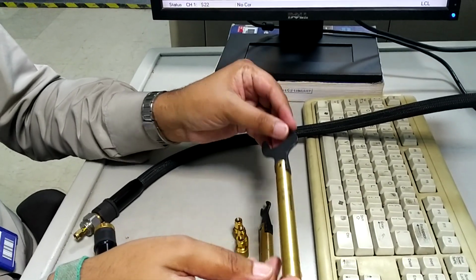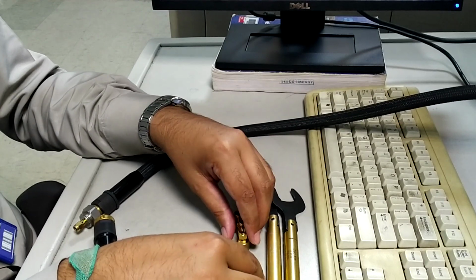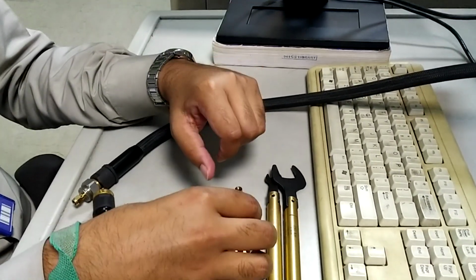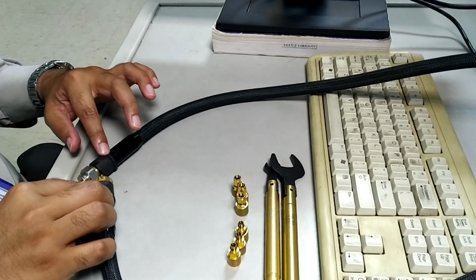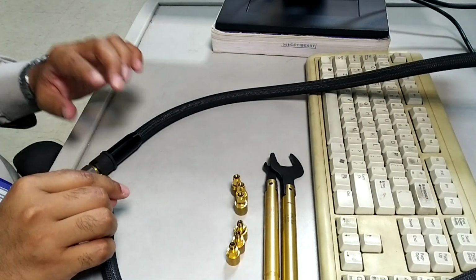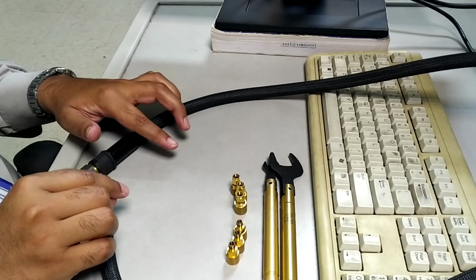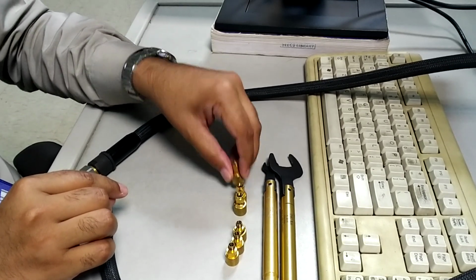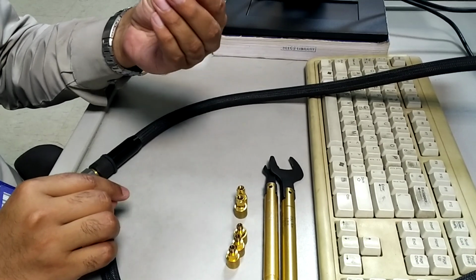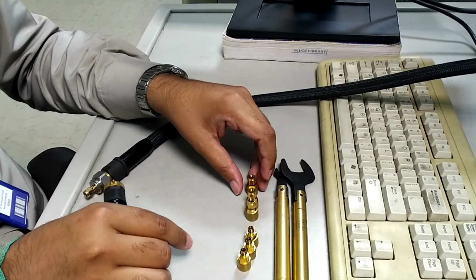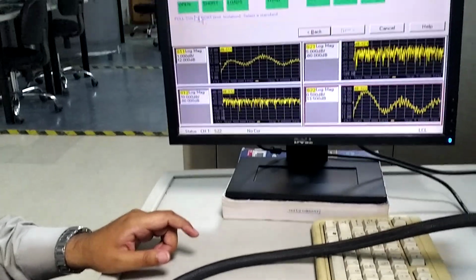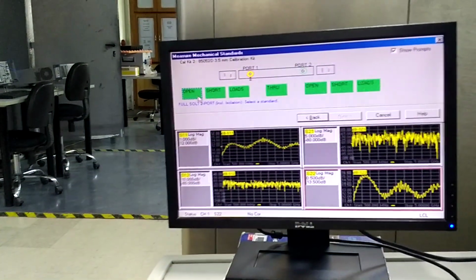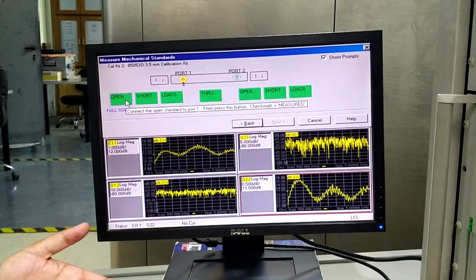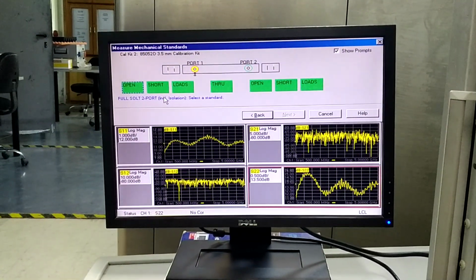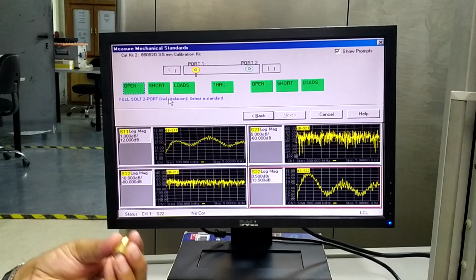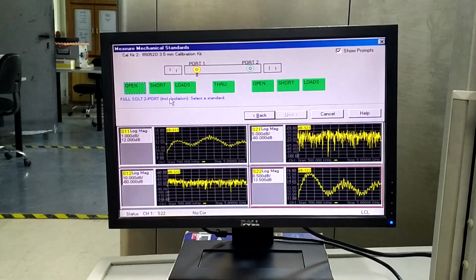So now here I will use these two torque wrenches and these one port calibration standards to perform the calibration, and for through I make a direct connection. So let's start by connecting the first calibration standard and doing the measurement. You can select any standard you want here. If you see the screen, there are open, short, load, but it's not necessary that you connect an open first. You can connect a short first, but the important thing is, once you have connected a short, you should select that you connected a short. So the VNA must know that a short is connected.